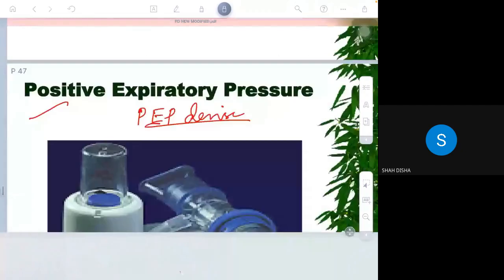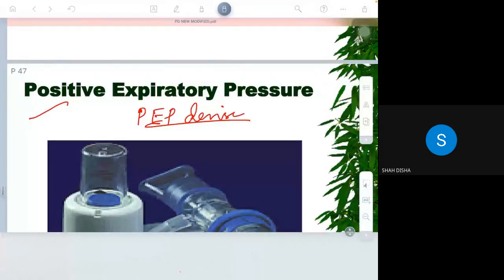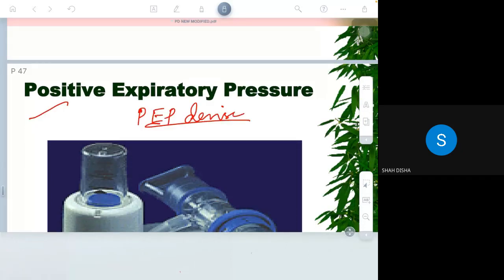PEEP devices allow the lungs to have positive pressure at the end of expiration. They do not allow the lung pressure to fall to zero — they maintain positive pressure even after completion of expiration. That is the advantage of this device.